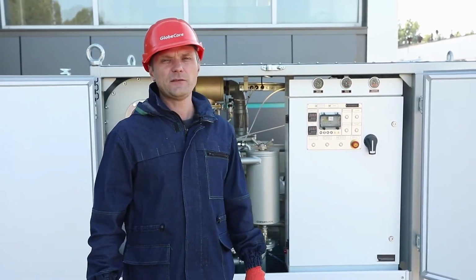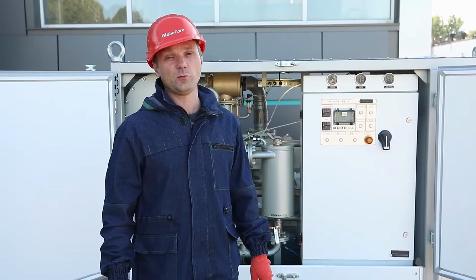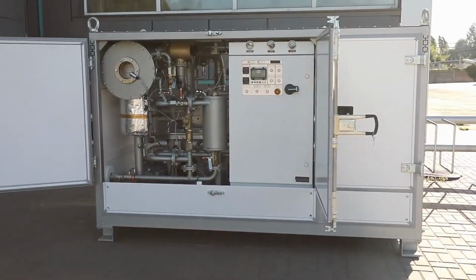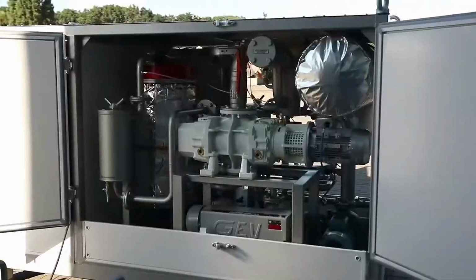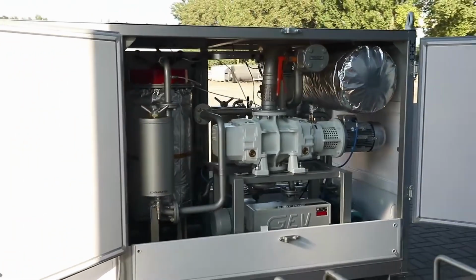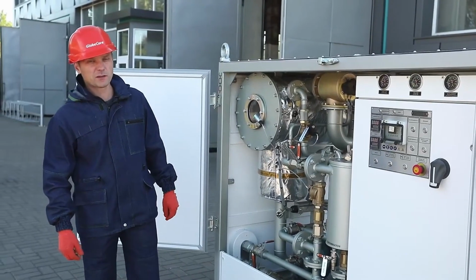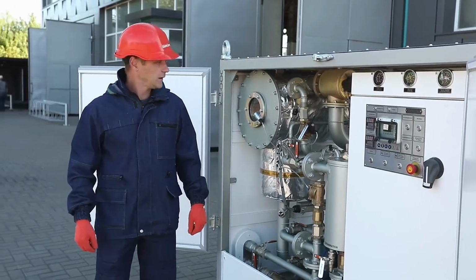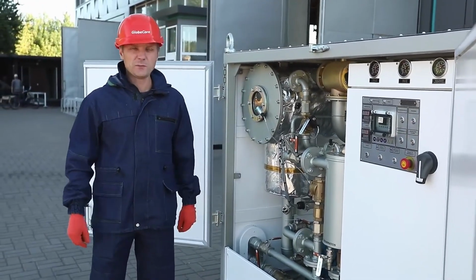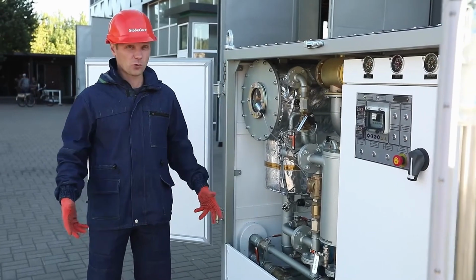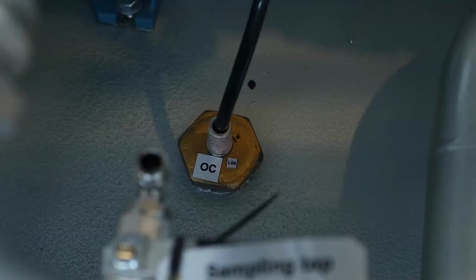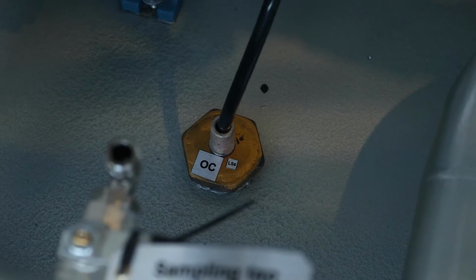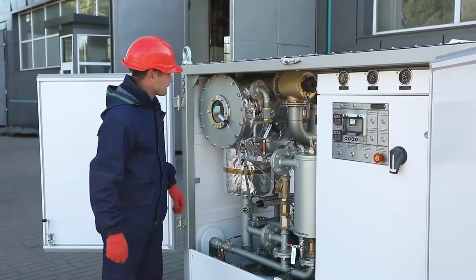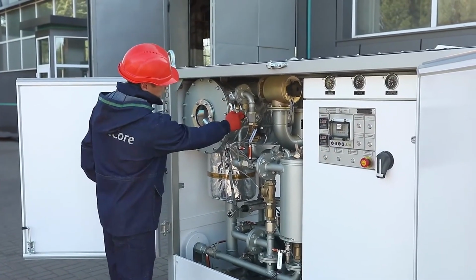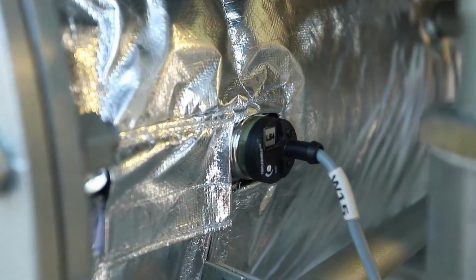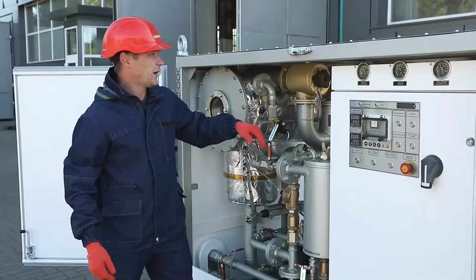Certainly, a more complex design requires additional sensors. Operating the CMM-6/7 unit, you can be sure that it is secured against abnormal situations. A float sensor is built in the spill tray of the unit to detect oil leaks. A foam sensor is installed in the vacuum chamber and prevents foam from entering the vacuum system. And a flow switch helps in stopping the oil pumps when there is no oil flow detected.